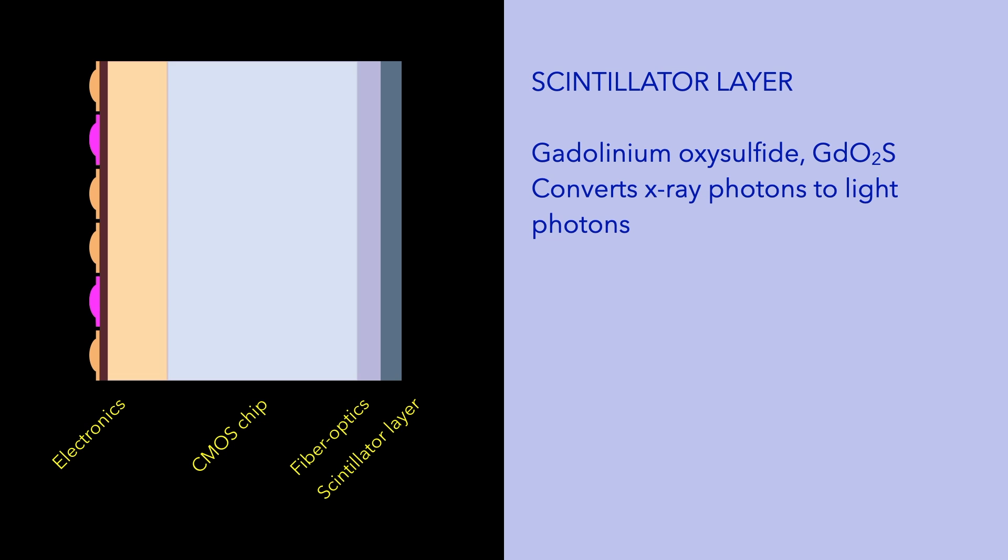Now let's take a look at the functioning of the sensor. When X-ray photons first strike the sensor, they encounter the scintillator layer. The scintillator layer is made up of a high atomic number element such as gadolinium oxysulfide, which very efficiently converts X-ray photons to light photons.